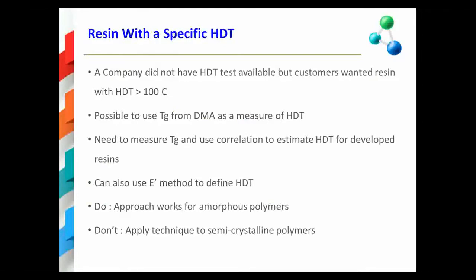Now I would like to discuss a brief case study that I was involved with that utilizes the type of information I was talking about on the previous slide. A company I was working with had obtained a request from one of their customers for a material that has an HDT value of greater than 100 degrees centigrade. Unfortunately, the company did not have an HDT testing unit, but they did have access to a DMA testing unit. They wanted to know how to relate their DMA test results to HDT values.